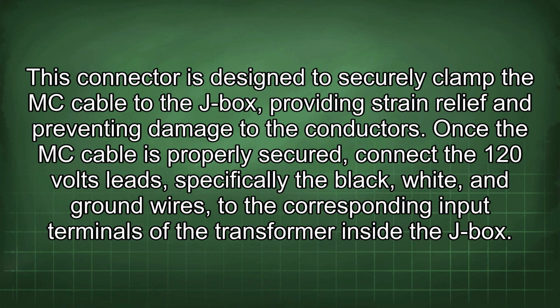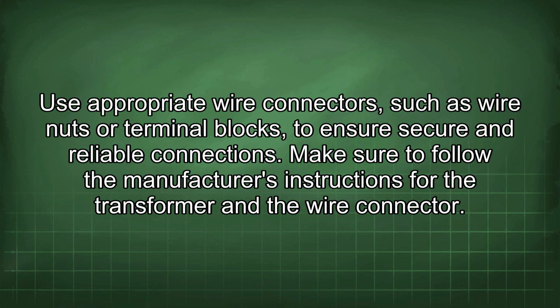This connector is designed to securely clamp the MC cable to the J-box, providing strain relief and preventing damage to the conductors. Once the MC cable is properly secured, connect the 120 volt leads, specifically the black, white, and ground wires, to the corresponding input terminals of the transformer inside the J-box. Use appropriate wire connectors, such as wire nuts or terminal blocks, to ensure secure and reliable connections. Make sure to follow the manufacturer's instructions for the transformer and the wire connector.